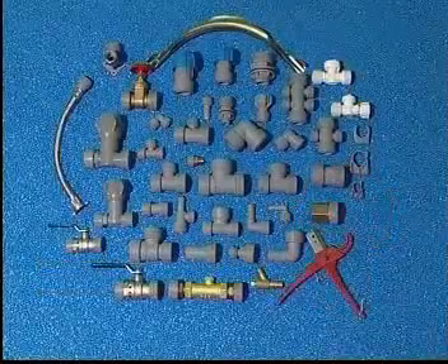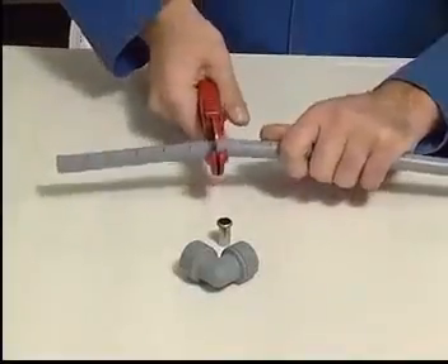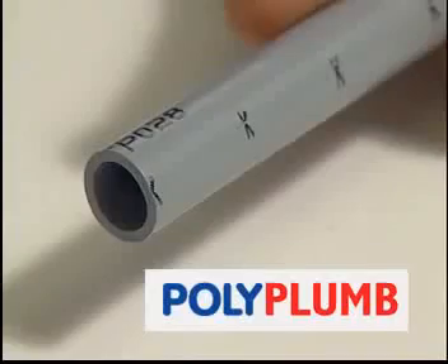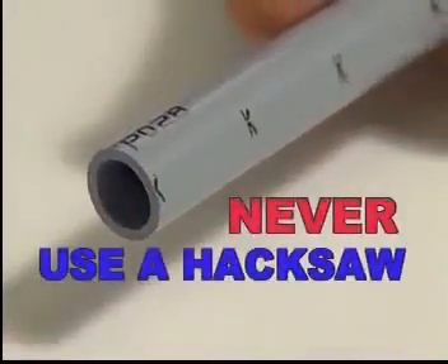The Polyplumb system is quick and easy to use and you don't need a blow lamp or expensive tools to fit. You simply cut the pipe to length using the space installation marks printed clearly on the side of the pipe. To do this efficiently, always use a polypipe cutter. Never use a hacksaw.